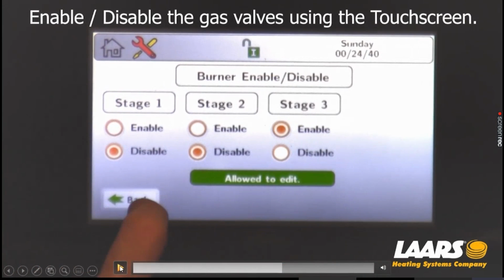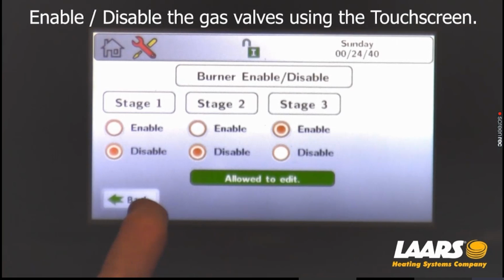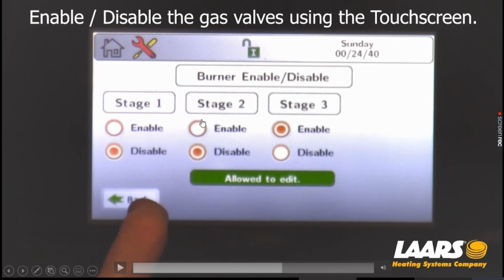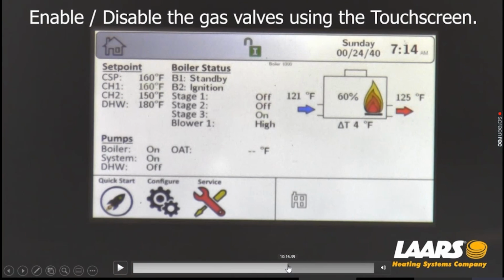So I'm going to stop the video and explain again. So your igniter is under stage 1, and a 4-stage boiler, your second igniter is going to be under stage 3. So if you tried to shut off stage 1, it automatically shuts off 2. Why is that? We don't want to energize or try and enable stage 2 where there's no ignition point, and the same for stage 4. You don't want to try and enable stage 4 where the igniter is under stage 3. So that is the only other thing that could be a little confusing.